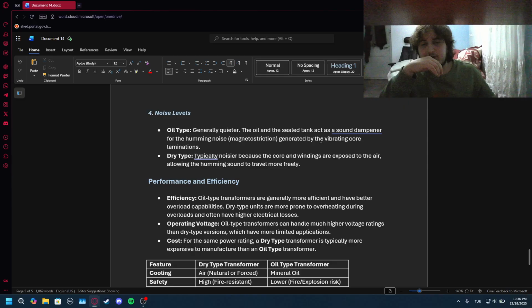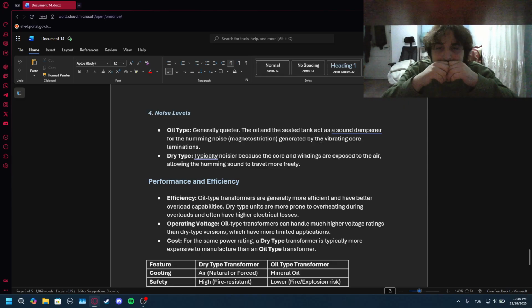Performance and efficiency. Oil type transformers are generally more efficient and have better overload capabilities. Dry type units are more prone to overheating during overloads and often have higher electrical losses. But the upside is they are really safe. Operating voltage. Oil type transformers can handle much higher voltage ratings than dry type versions, which have more limited applications.